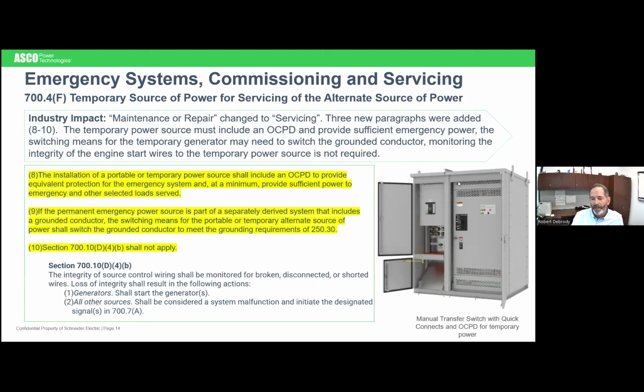Off to the right here, this is just an example of a product that would do this. You can see in the bottom left is where you would hook up a temporary generator to the cam locks, and above that is the circuit breaker, and off to the right is the manual transfer switch that you would use to transfer from the permanent source to the temporary power source.